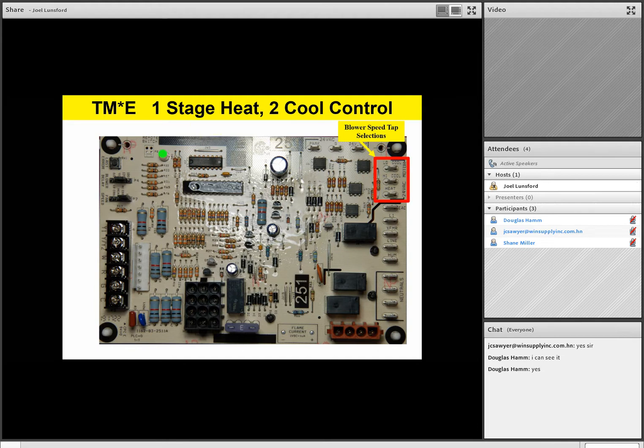Now it should be noted that we always ship these on the highest possible speed from the factory. However, once the install technician hooks the furnace up, he's going to want to make sure he selects the proper speed tap to provide 400 CFM per ton of cooling capacity of the outdoor unit. And so when he sets up his high cool speed, if he's on a 2-stage unit, it needs to be for 400 CFM per ton.